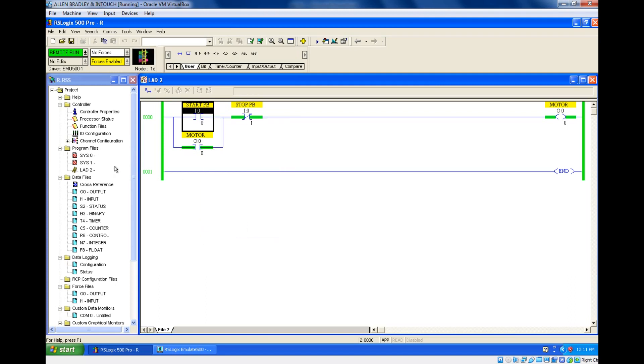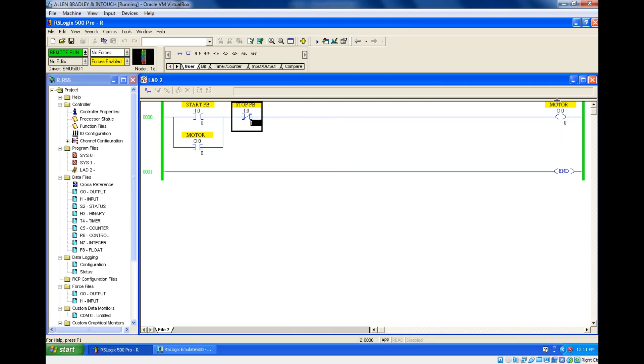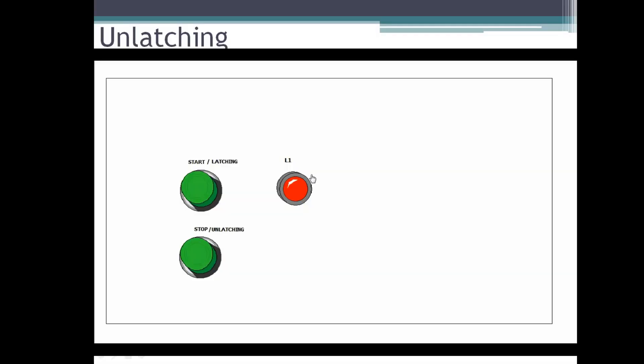Why am I using the second push button? If you use the same input it will not have any influence after the latching. So once it is latched you should connect one more input after the latching — you turn on this stop push button which will unlatch your motor. Check it out: I'm turning on, it got turned on, and if you press the stop it will be off.